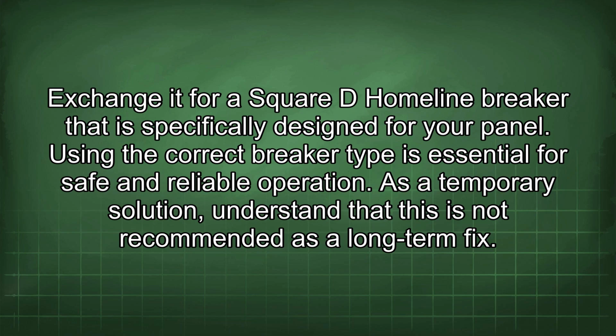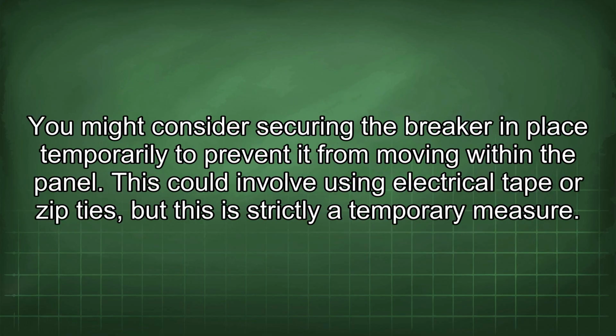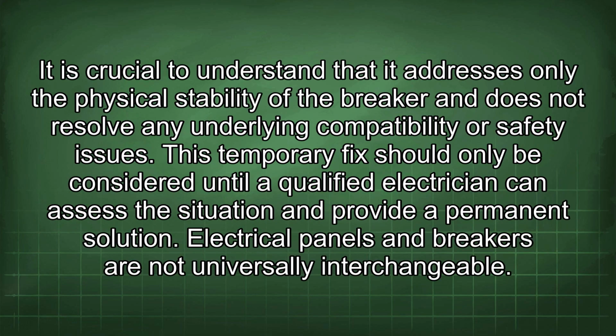As a temporary solution, understand that this is not recommended as a long-term fix. You might consider securing the breaker in place temporarily to prevent it from moving within the panel. This could involve using electrical tape or zip ties, but this is strictly a temporary measure. It is crucial to understand that it addresses only the physical stability of the breaker and does not resolve any underlying compatibility or safety issues. This temporary fix should only be considered until a qualified electrician can assess the situation and provide a permanent solution.